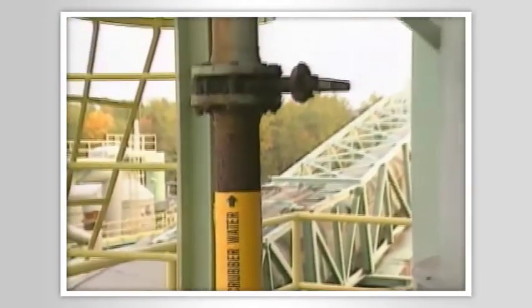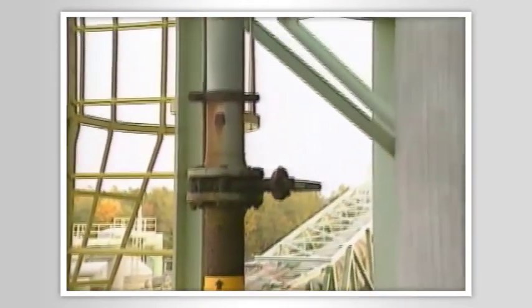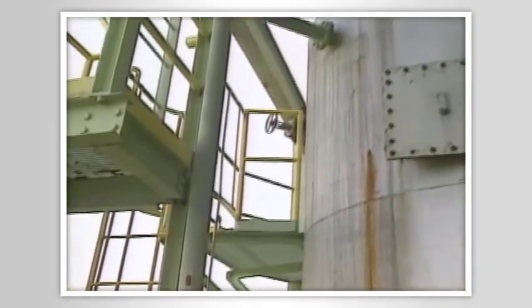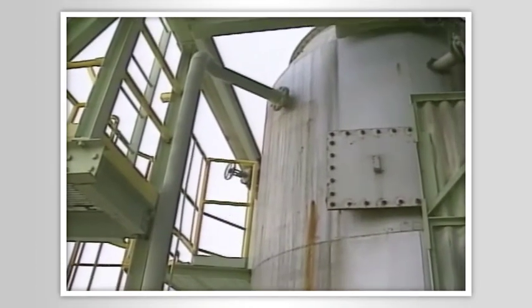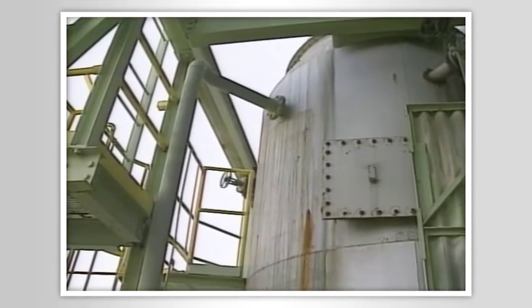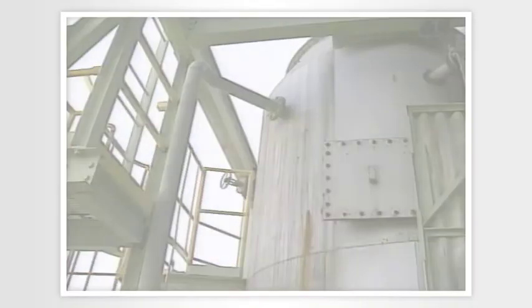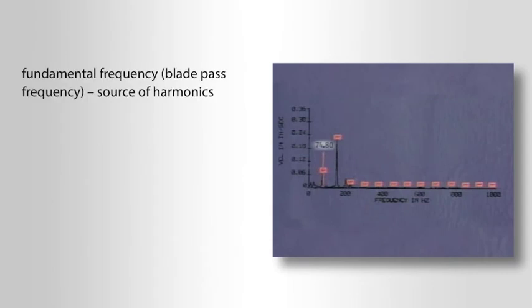Because resonance was suspected, additional braces were welded to the fan casing to stiffen the assembly, but they did nothing to quiet the vibration. The evidence suggests that the vibration in the fan increases as the flow of water increases and appears unrelated to the turning speed of the shaft, which remains constant. We also know that the fundamental frequency — in this case, the blade pass frequency — is the source of the harmonics.